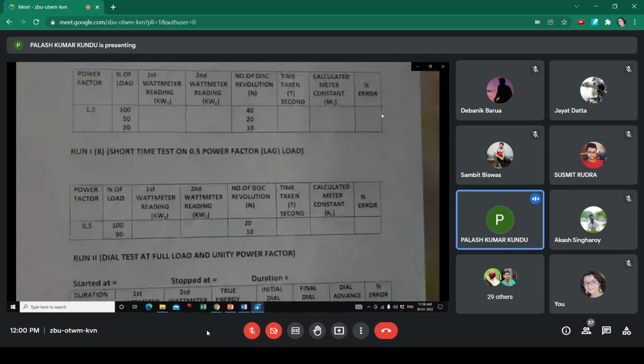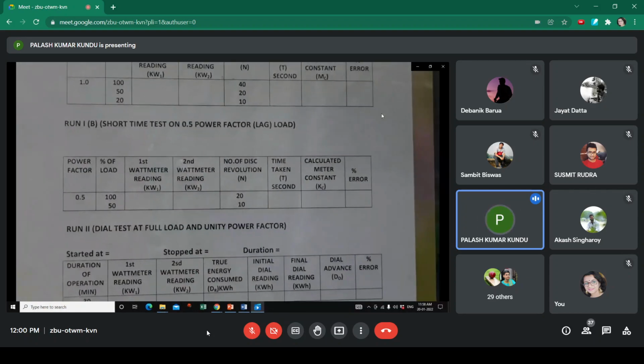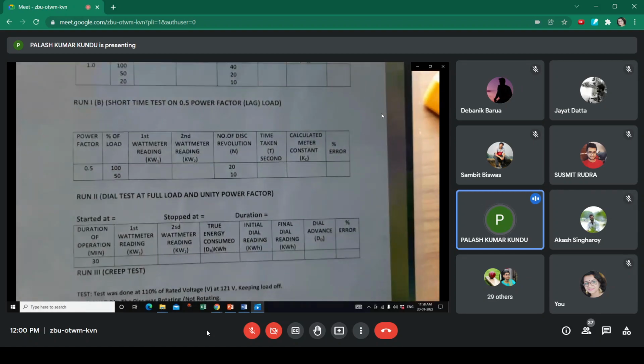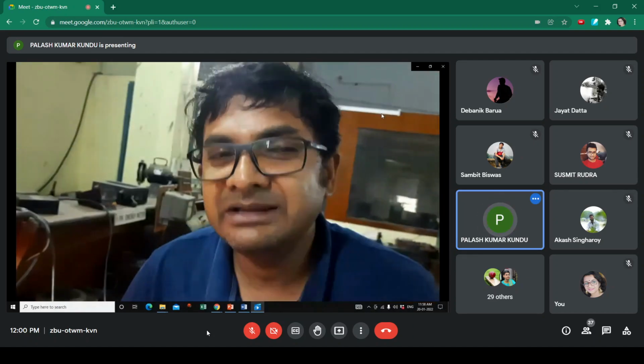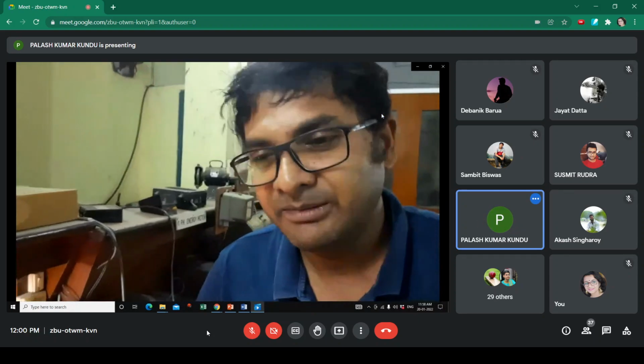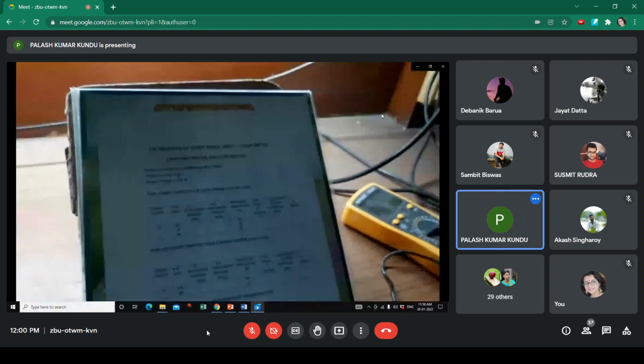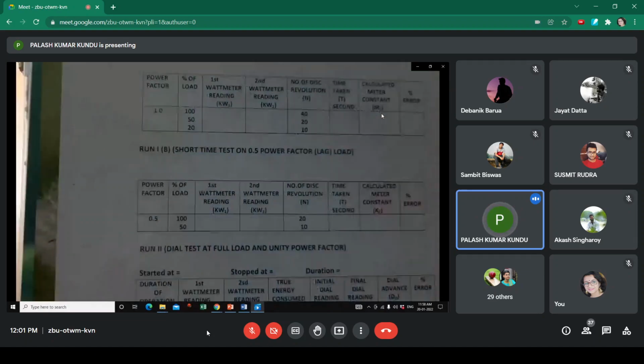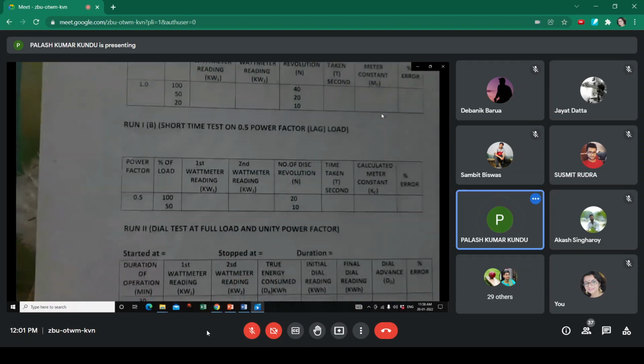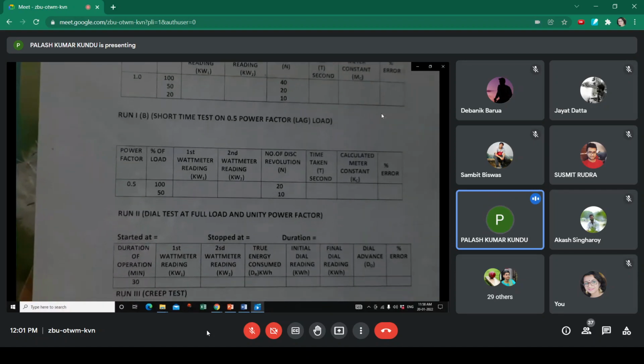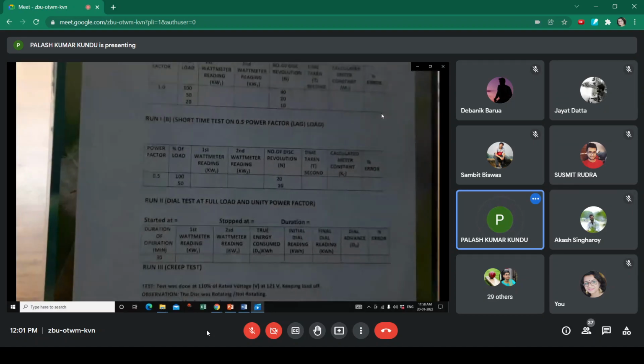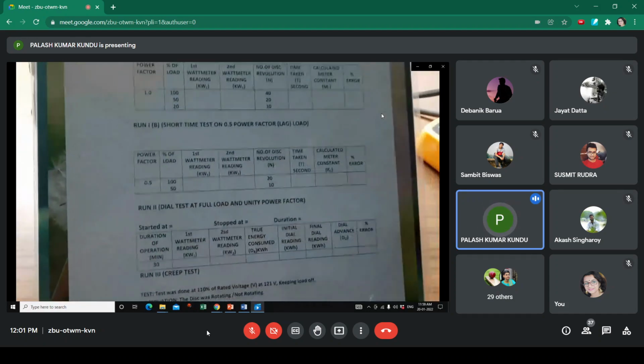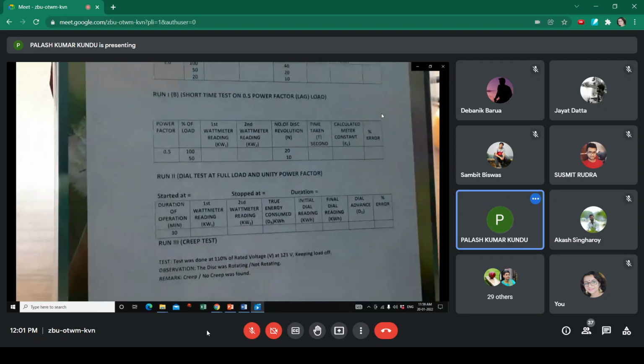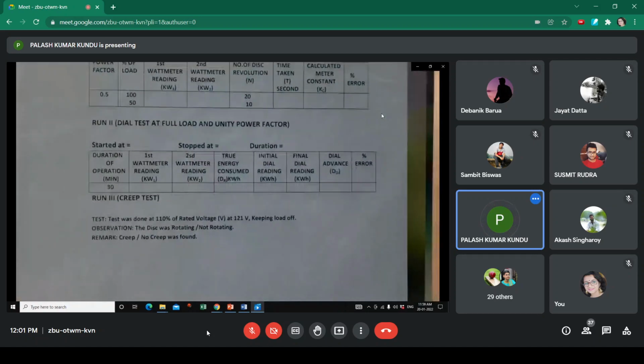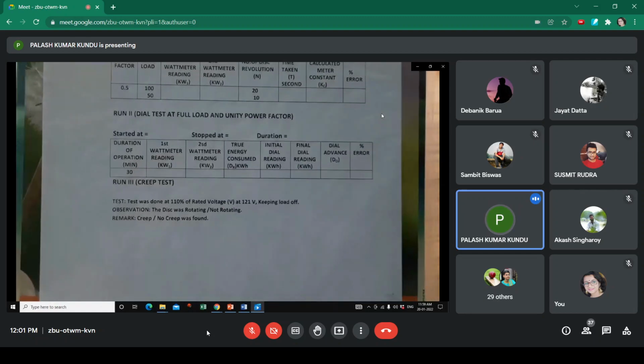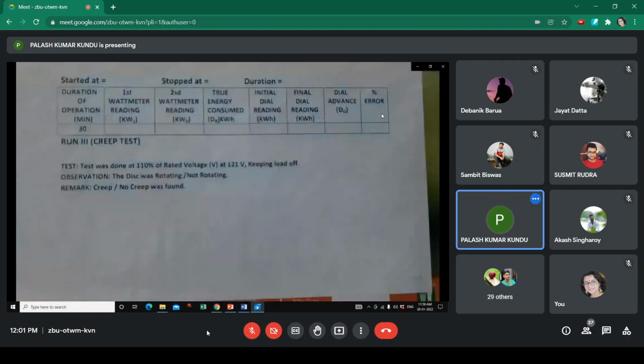Okay. Now run 1B, the second part of the first one. First of all, in this run 1B, we will change the value of the power factor. How? Already I told you, we'll make the value of the power factor 0.5, by changing the phase shifter. Then at 0.5 power factor for 100% load, we'll take the time again. We'll take the time for 20 revolutions of the disk, and at 50% of the load, we'll take the time for 10 revolutions of the disk. So our run 1B is the short time test at 0.5 power factor. Okay. Then the next test is run 2. Run 2 will be the dial test at full load, unity power factor. Okay. And the third and the last test will be run 3, that is the creep test.